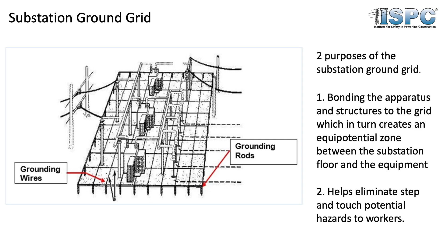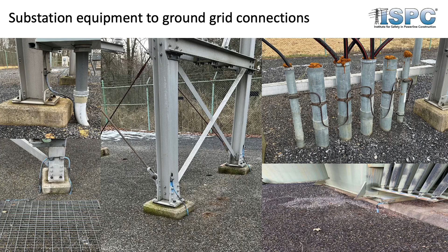Once we're inside the substation fence doing whatever we're there to do, inspection, switching, or work, we need to be vigilant and check the connections from the grid to our equipment. You can see in a couple of these pictures the substation ground tails coming up to the structures appear blue. Well, they are blue, that was a utility's way of trying to prevent theft.